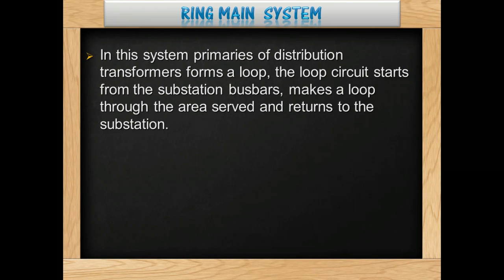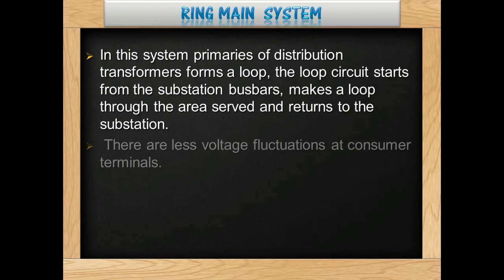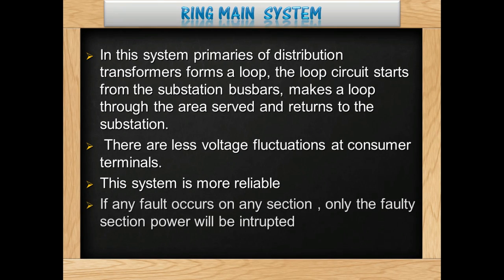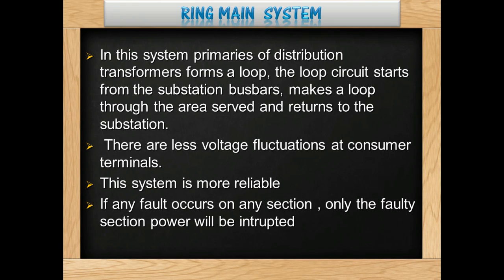Coming to the ring main system: In this system, the primaries of distribution transformers form a loop. The loop circuit starts from the substation bus bars, makes a loop through the area served, and returns to the substation. There are less voltage fluctuations at consumer terminals, and this system is more reliable. If any fault occurs on any section, only that faulted section's power will be interrupted.